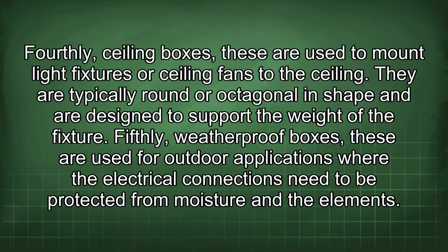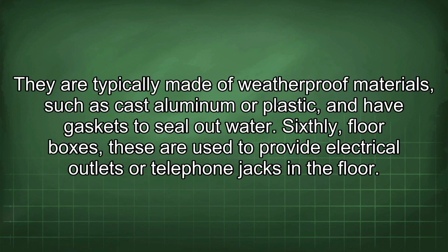Fourthly, ceiling boxes. These are used to mount light fixtures or ceiling fans to the ceiling. They are typically round or octagonal in shape and are designed to support the weight of the fixture. Fifthly, weatherproof boxes. These are used for outdoor applications where the electrical connections need to be protected from moisture and the elements. They are typically made of weatherproof materials, such as cast aluminum or plastic, and have gaskets to seal out water.